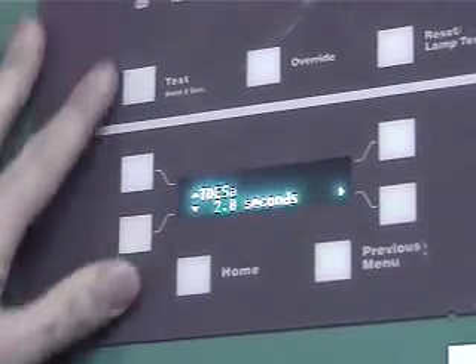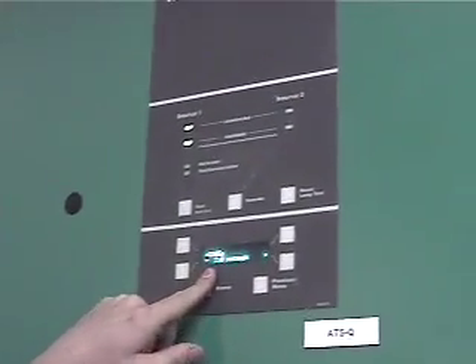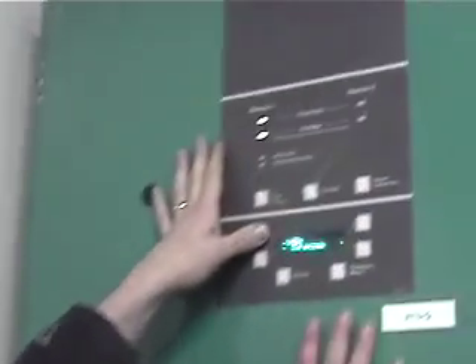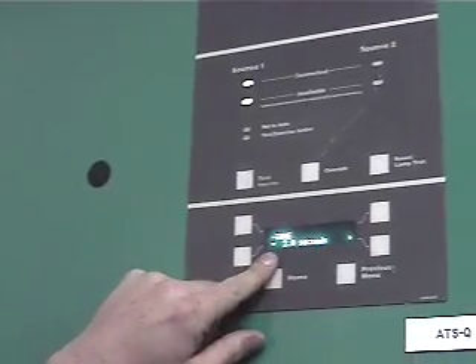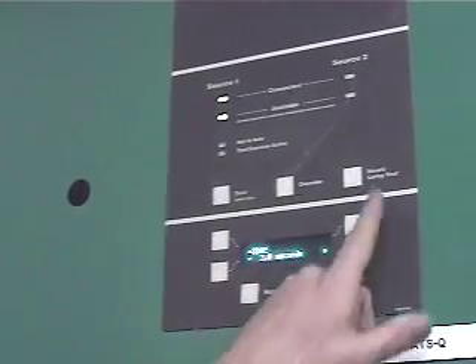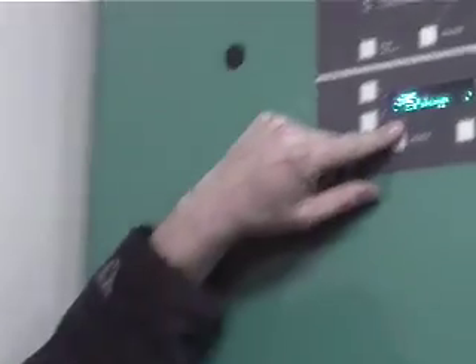The very first time delay is our time delay engine start. When the power goes out, if it's out for 2 seconds, after that 2 seconds I'm going to tell the generator to start. If it's just a real quick bump, we don't want to go on generator. It's only going to be out for a second. Let's not go to generator. Now, if it's out for 2 or 3 or 4 seconds, yeah, let's see what's going on. If it's out for 2 seconds, the generator will start cranking. Once it comes up to speed and becomes available, it'll then go into this normal to emergency time delay. So the generator comes available, and 2 seconds later it's going to transfer over to gen.